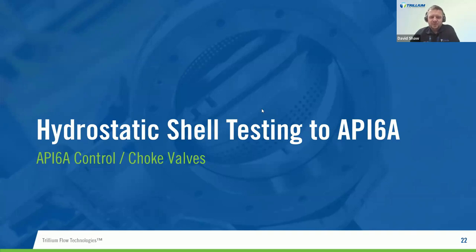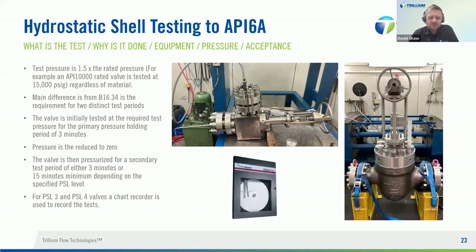Hydrostatic shell testing to API 6A — for the valves we do here at Elland, this applies mainly to choke valves, though within other Trillium companies we have API 6A ball valves tested in a similar manner. The actual testing is similar to the B16.34 shell test. The test pressure is 1.5 times the rated pressure. It's simpler to apply on API-rated products because you don't have the different material groups and you're generally not dealing with elevated temperatures. An API 10K rated valve, for example, is tested at 15,000 PSI regardless of material.